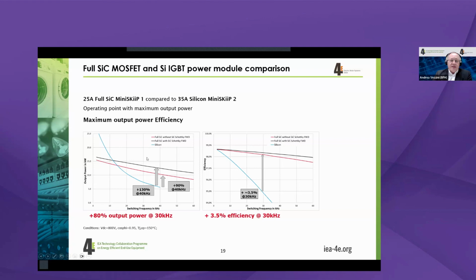When you look now at full SiC, the red line is without the diode, the black line is with the freewheeling diode. As you can see, it's a better performance, and the impact of the switching losses is much less. Especially at higher frequency, we have an advantage of the silicon carbide modules. This advantage in total output power, for a given loss amount, is translated directly into efficiency. When we are at very low switching frequencies, like 4 or 5 kilohertz, there is not such a big difference between these two semiconductor devices. But as soon as you increase the switching frequency, we see a decrease in efficiency, and we therefore have an advantage of silicon carbide.